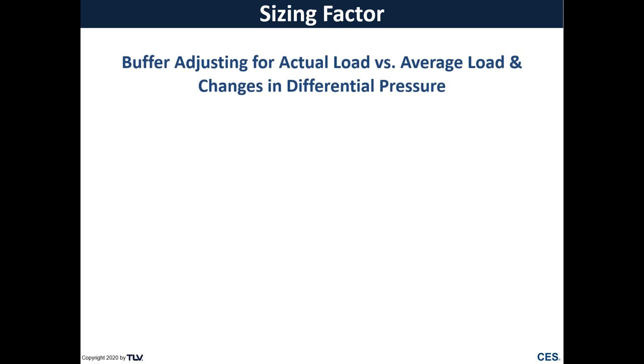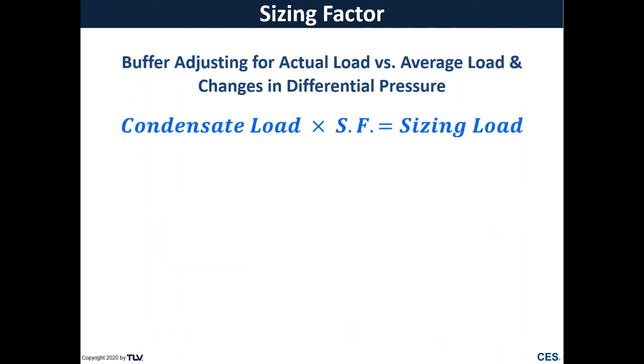Another important factor for condensate load is our sizing factor. Our sizing factor is basically going to be a buffer between what our actual conditions are versus maybe some changes that we may see due to differential pressure or maybe a maximum startup load. So typically we'll take our calculated or specified condensate load, multiply that by a sizing factor to establish our sizing load. And this is going to vary based on the type of steam trap we have.